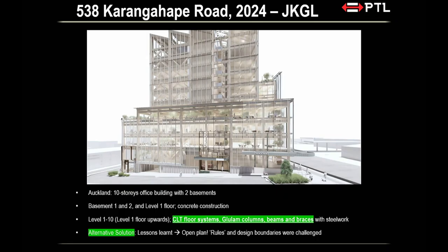So it's an alternative solution, and it presents a very big challenge because if you look at all the case studies before, it's all small rooms. It's all small apartments we talk about, you know, it's guaranteed full room involvement because it's so small. A lot of our design calculation is empirical and analytical in nature, and they've been developed for small rooms. Now you apply that here, it's a bit of a stretch, right? And you've seen already that 300 square meter compartment, how quickly the fire gets to the end in the last 40 seconds, like what would happen here? So I don't have all the answers. I'm the designer for this, unfortunately.